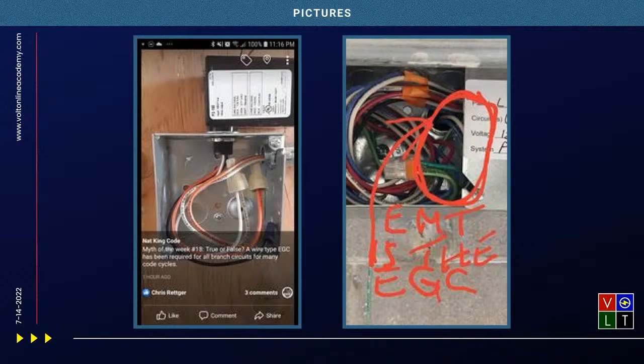The other problem is that when we're coming through there, we had to come through an nLight control cabinet, through a relay section. So per code, if I was to pull a wire through there, that wire would be required to be bonded at that relay cabinet. Then you open up a can of worms, because now I hit the ground screw on this 4-square, I've got to go through the relay cabinet, I have to tap my own 10-32 or whatever thread count it could be anything, and it doesn't have to be green either. So we might do that for one.